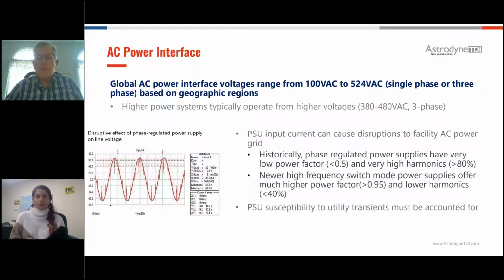Certainly, newer high frequency switch mode supplies typically operate at a much better power factor than you would have seen in the past. Thyristor control supplies had power factors of around 0.3 to 0.4, and harmonics upwards of 80% of the fundamental line current. Whereas a high frequency switch mode supply is generally going to have a power factor greater than 0.95 and harmonics well below 40%. So you need to keep that in mind. And as I said, the power supply in these industrial environments can have some really difficult AC line conditions that it needs to be able to survive. So susceptibility to utility transients, and to undervoltages and overvoltages caused by other equipment or other events within the facility, must be taken into account if you're looking for extended reliability and uptime for the equipment.